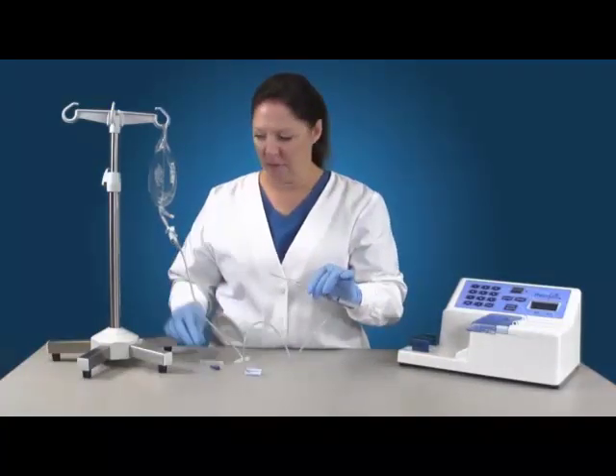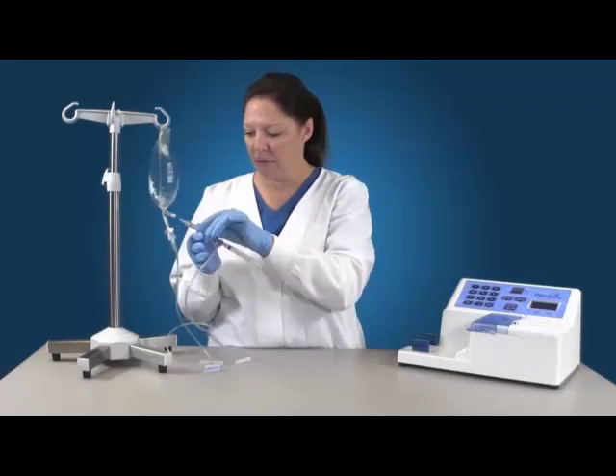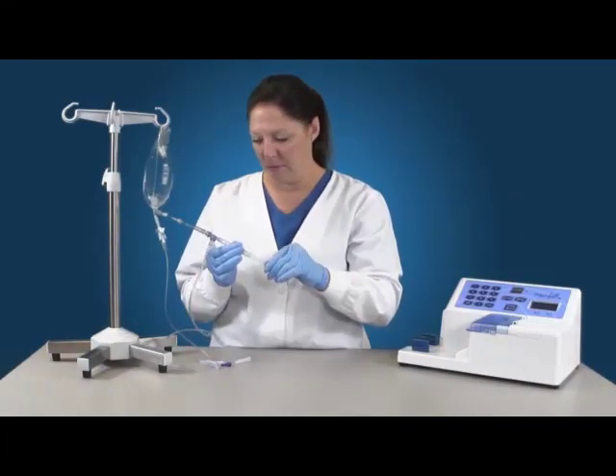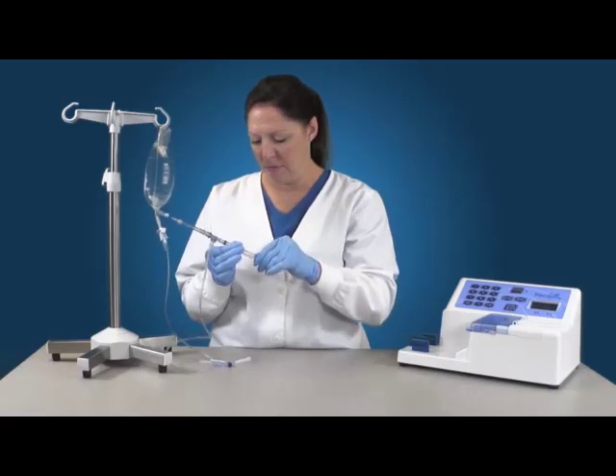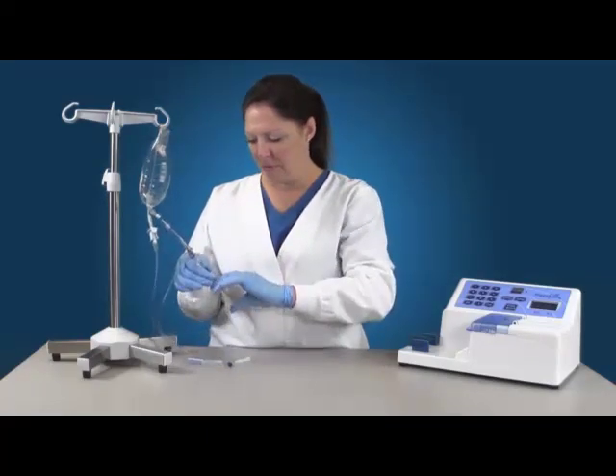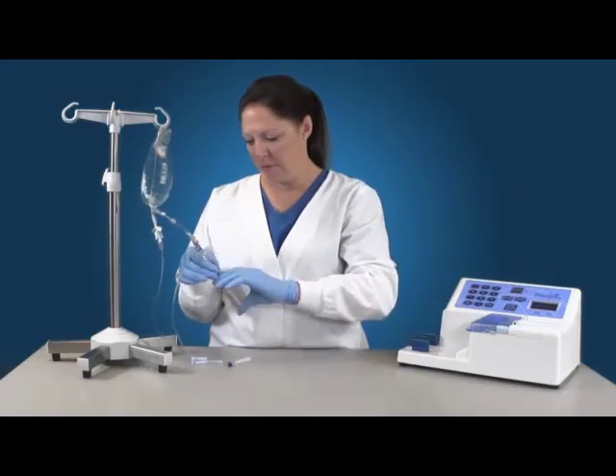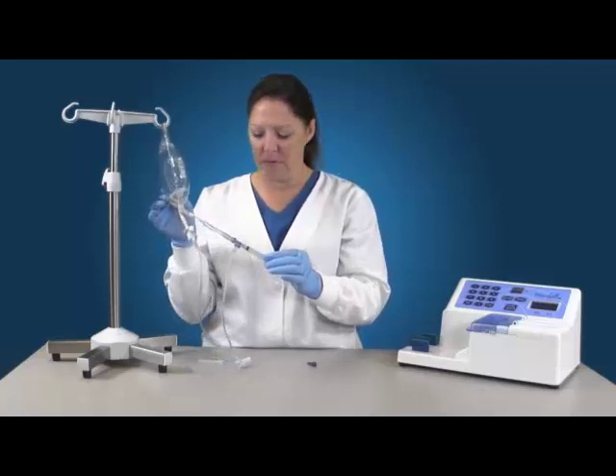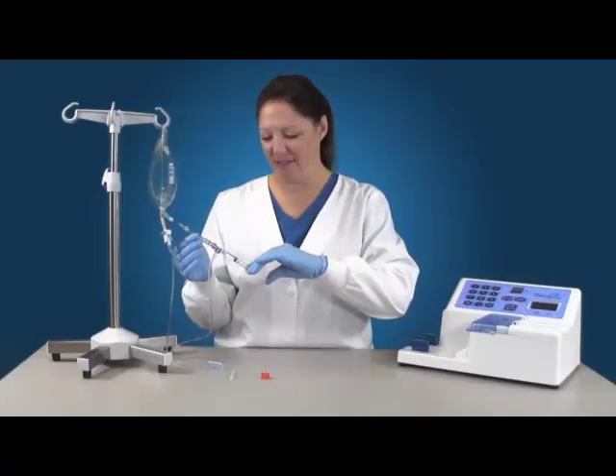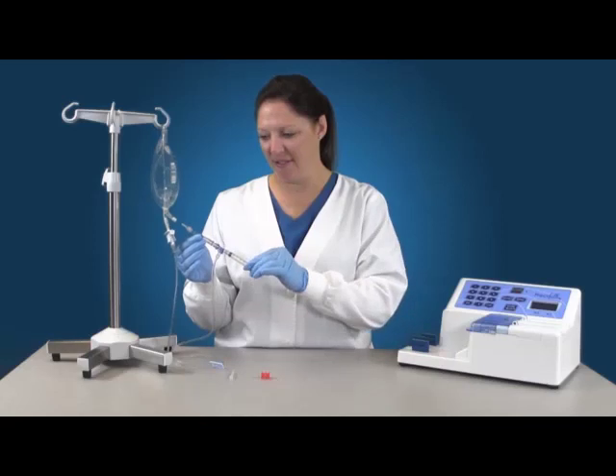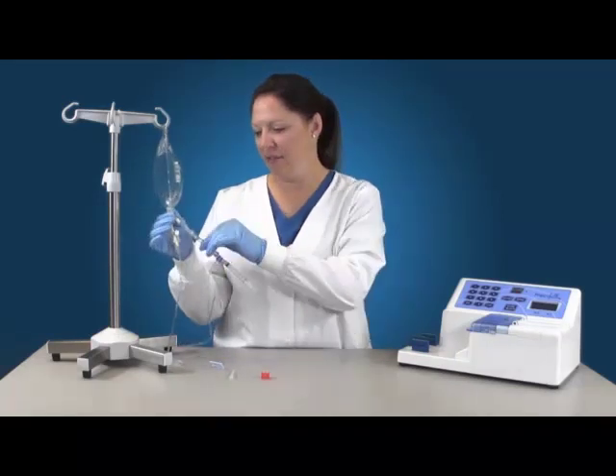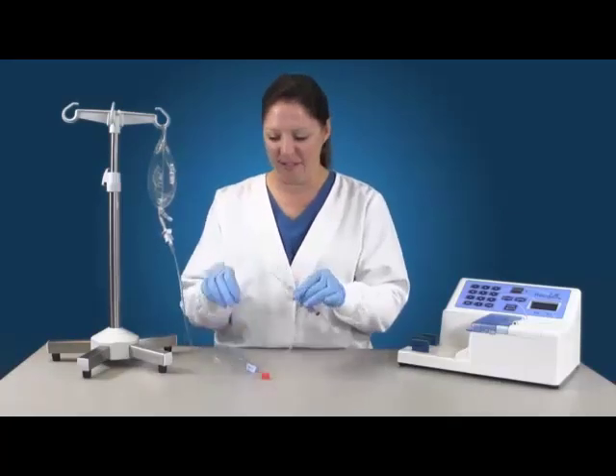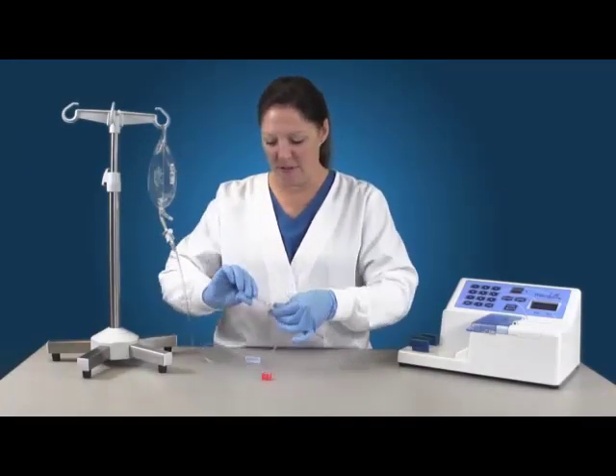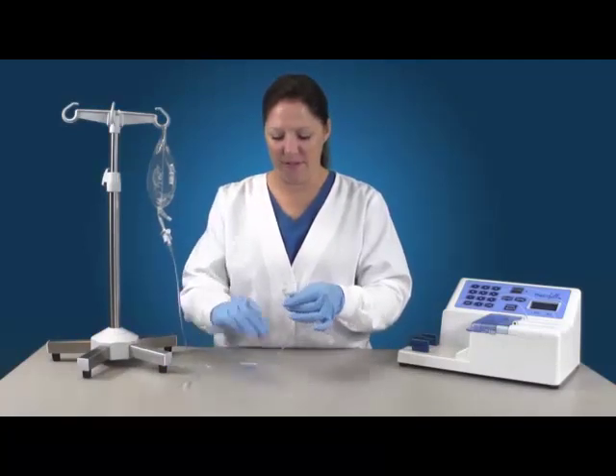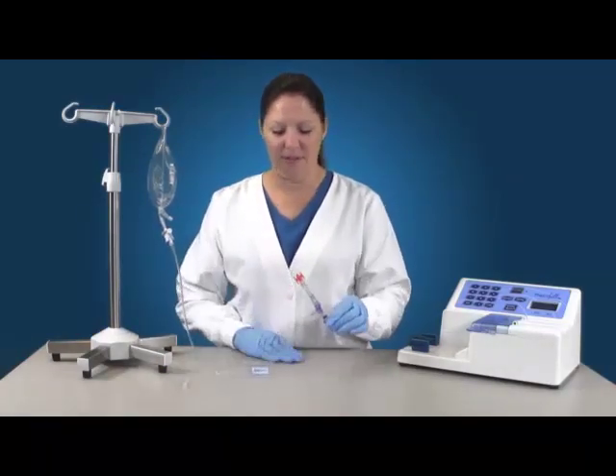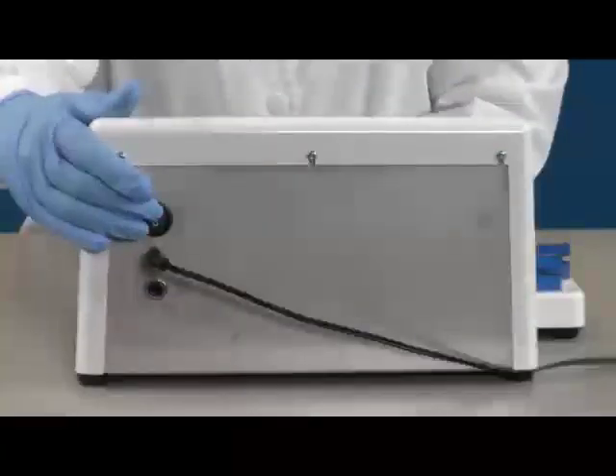Place the needle into the injection port and draw back on the plunger on the master syringe to expel air. Repeat this process until the tubing is filled with liquid and all air is removed from the master syringe. Fully compress the master syringe once priming is complete. Remove the needle from the injection port, and then remove the needle from the tubing set and discard. Attach the sterile IV adapter onto the tubing set. From the back of the pump, turn the power on.